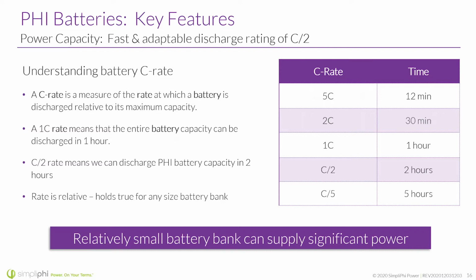For comparison, lead acids oftentimes might be rated at C/10, C/20. And what it means for us as far as charge and discharge goes is that we can actually charge or discharge. So let's say our 3.8 kilowatt battery, the best example here, we can charge or discharge 1.9 kilowatts continuous at a time. And when you add more batteries, that number continues to go up.